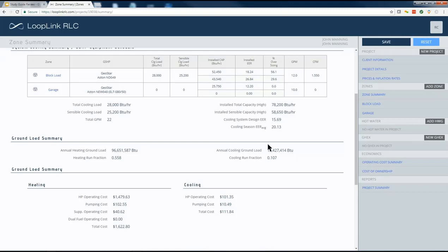This is how much we return back to the ground loop in the summer cooling season. We've got a fair amount of ground load imbalance here because we heat so much more than we cool, and that's a number that you'll see reflected in the ground loop design here when we get to it in a second. So, are there any questions on that so far?